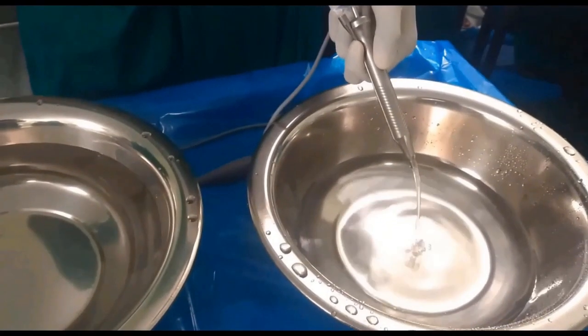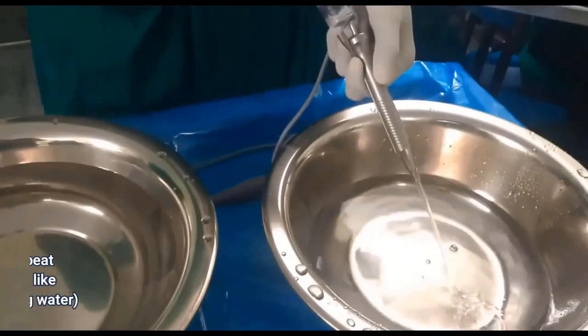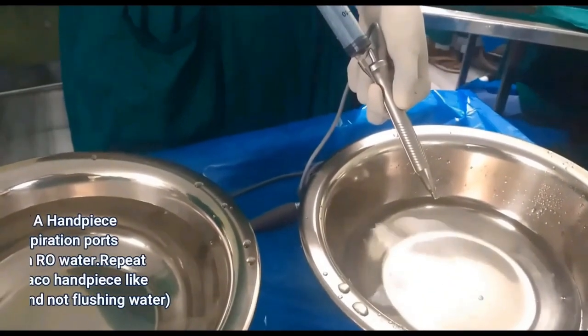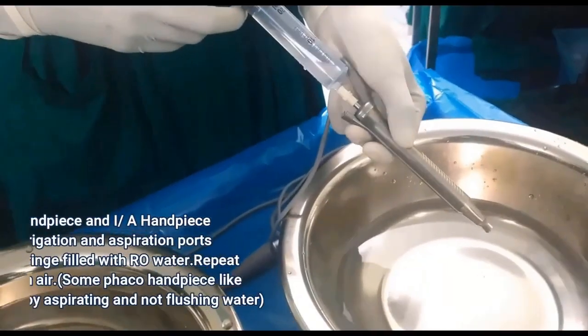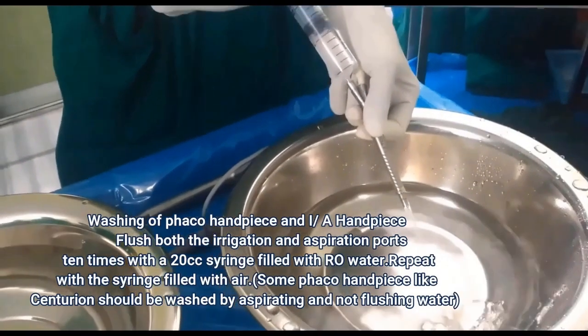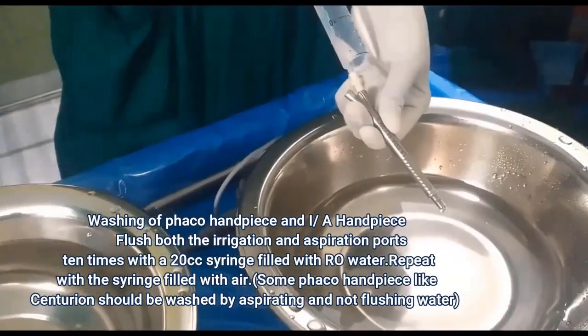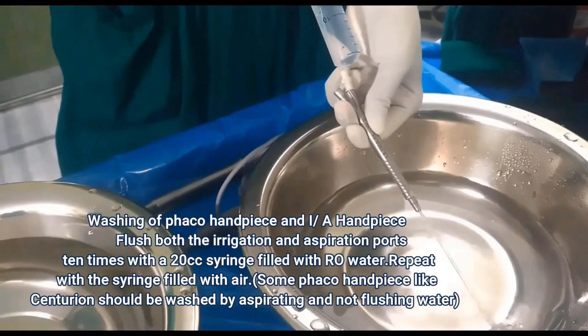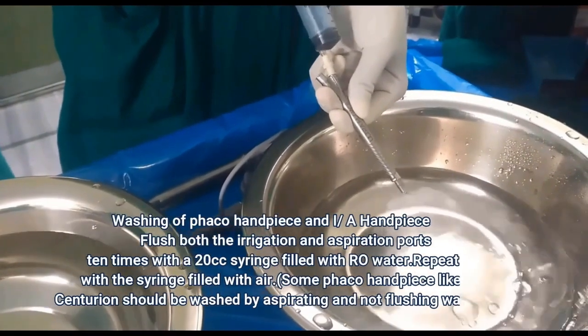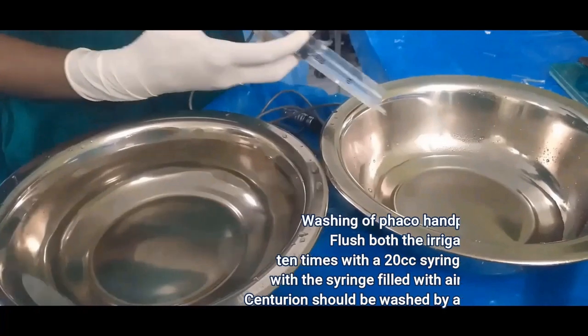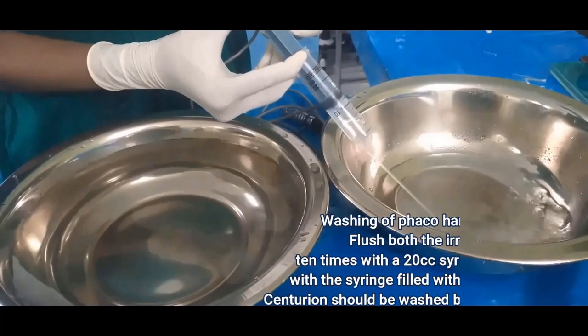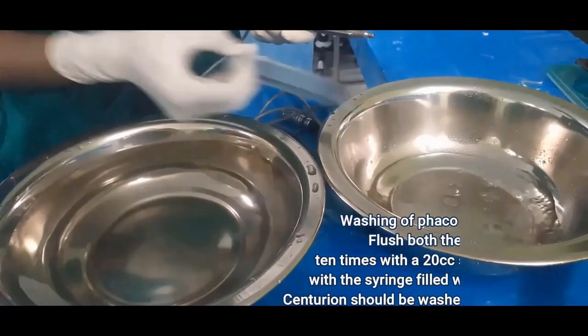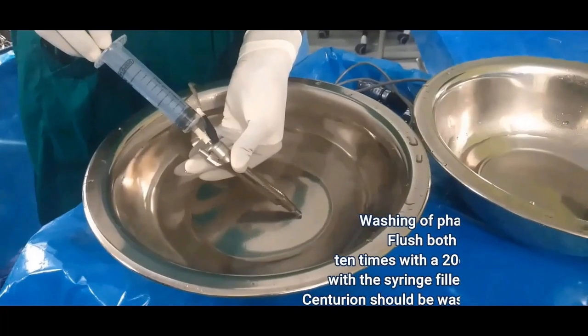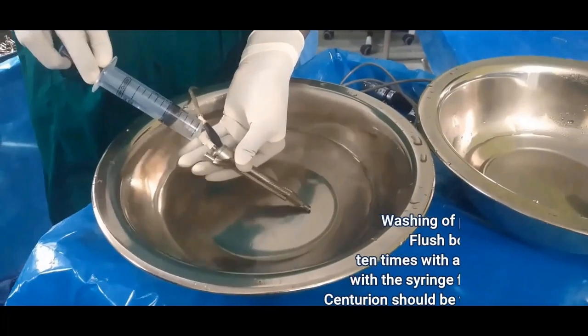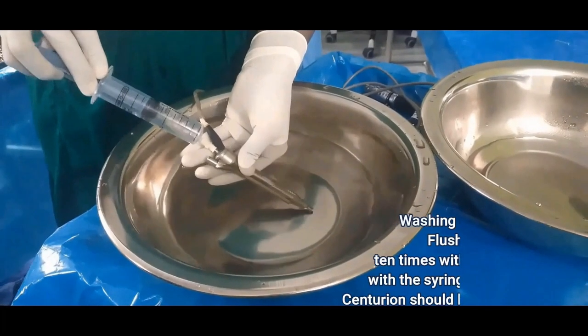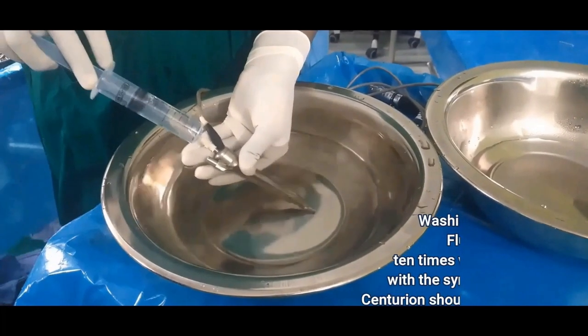Next comes washing of the phaco handpiece and irrigation aspiration handpiece. First, for the irrigation aspiration handpiece, flush both the irrigation and aspiration ports 10 times with a 20 cc syringe filled with RO water. Then repeat with a syringe filled with air. Washing of the phaco handpiece: it has irrigation and aspiration ports. The irrigation port is washed by flushing filtered water and the aspiration port is washed by aspiration of filtered water.